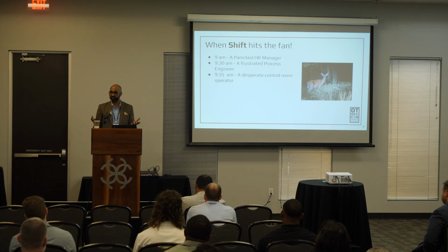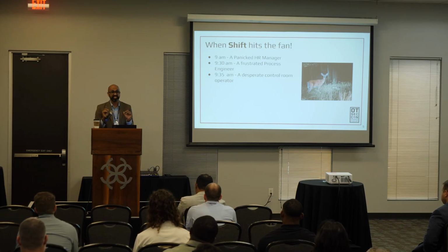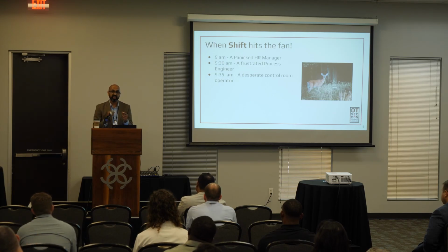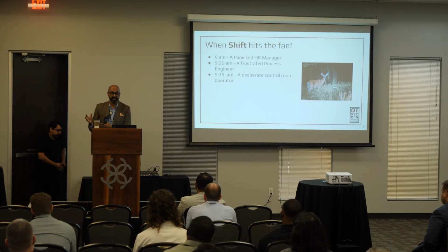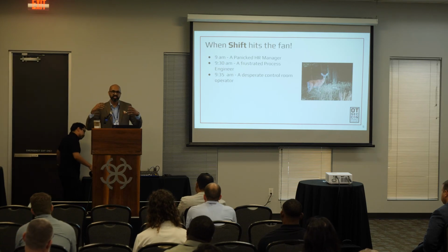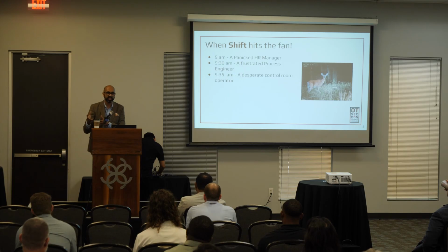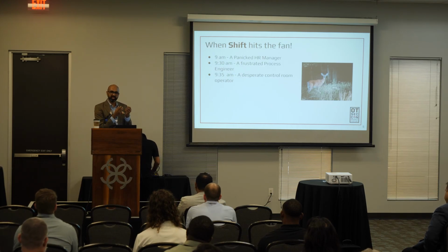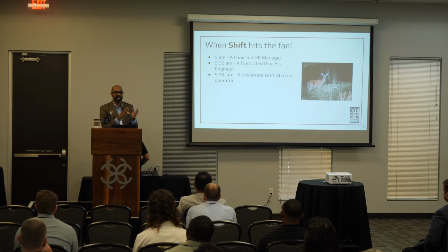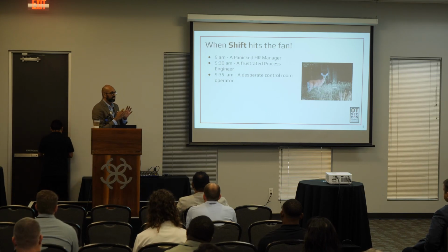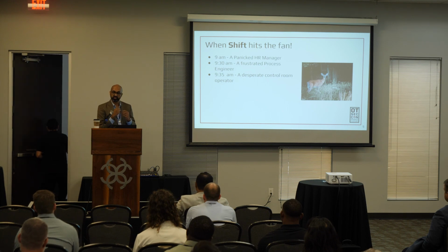And it's a desperate operator, saying, hey, the trends on my screen are glitchy. And I've heard this before. They can flatline if they have network issues with the Historian, right? So everybody's familiar with some of the PIs and some of the eXaquantums out there that provide you with some kind of historic data. But then operations uses it for real-time operation, right? So we have seen all that, and they were relying on this trend, which is glitchy.